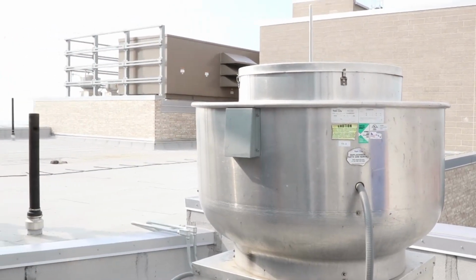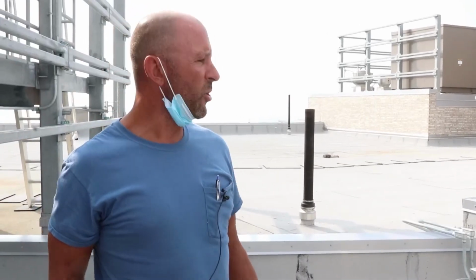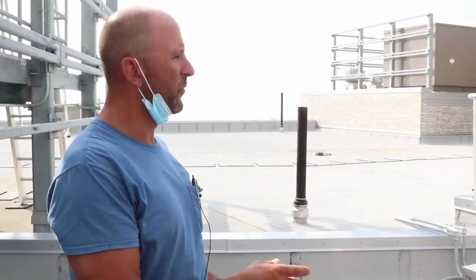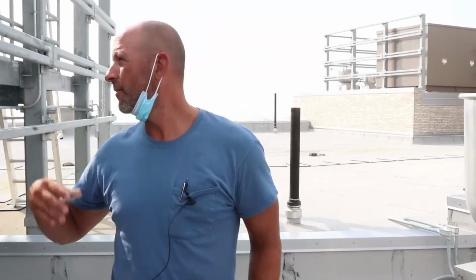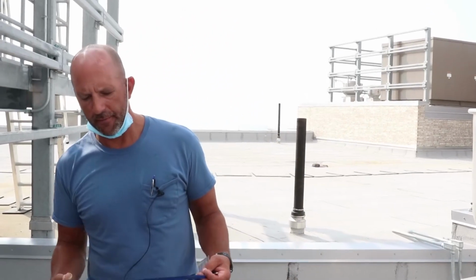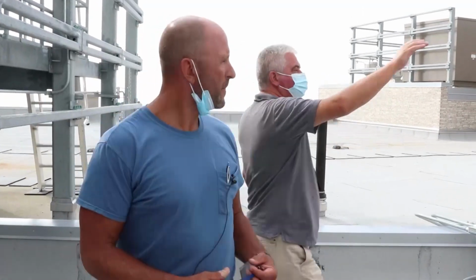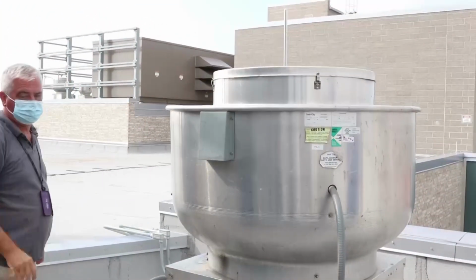Other than that, you would just have to know on a drawing what fan serves what. And like Mike said before, 1, 2, and 3 kind of match the units. Number 4 doesn't, number-wise. It's just the way they labeled the fans. But for every fan on an as-built, we'd be able to tell exactly what it does. Toilet exhaust, and I guess a general exhaust. This one does one grill in the laundry room all the way down, where this one does multiple bathrooms. All belt driven, like you said.